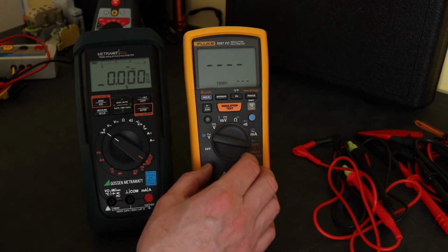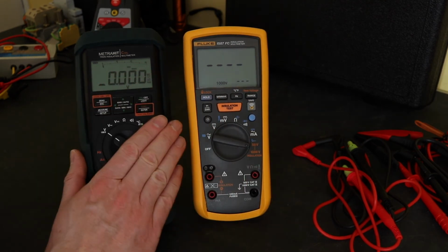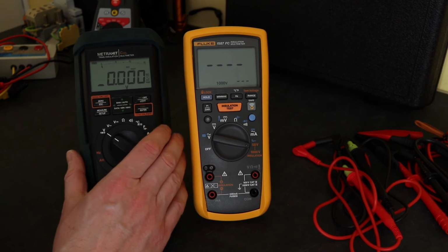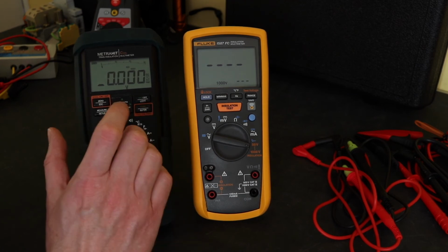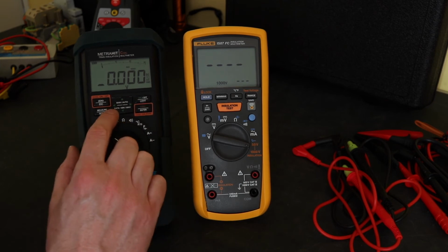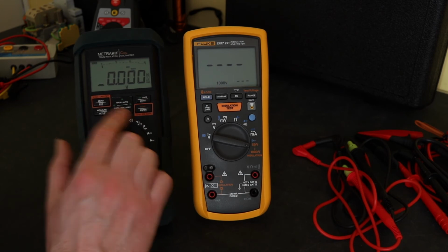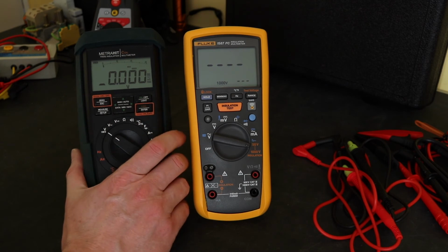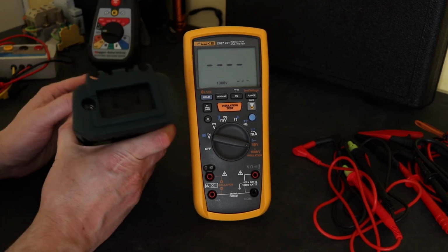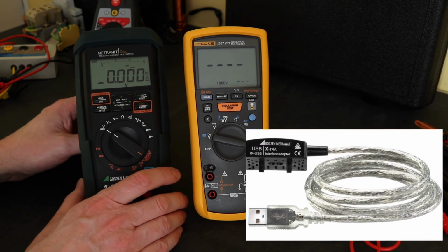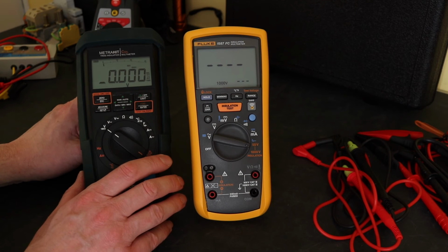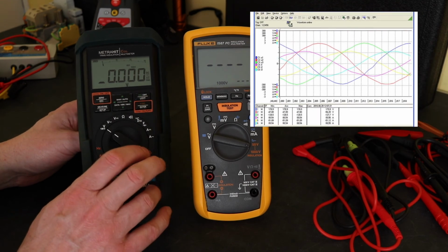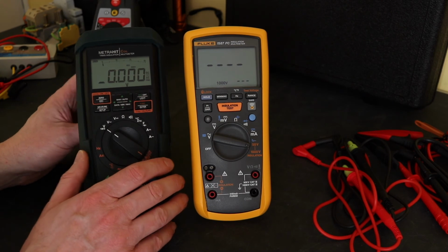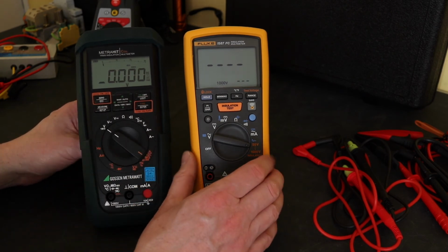But the basic test, which covers most of my needs to be honest, is free on the Fluke Gossen Metrawatt. I hope you've got a bit more money left, because this will transmit data as well, and it will also have its own internal memory for data logging. You can see the main function button there, and you can set up a record value on this to record internal data. However, if you want to get it off, it's an external adapter, IR adapter, that plugs in there. That will set you back another £230-ish. That plugs into a USB Windows only computer, and the software will set you back around about £210. So that's an awful lot of money you need to add to this to bring it up to the same kind of testing capability over the Fluke.